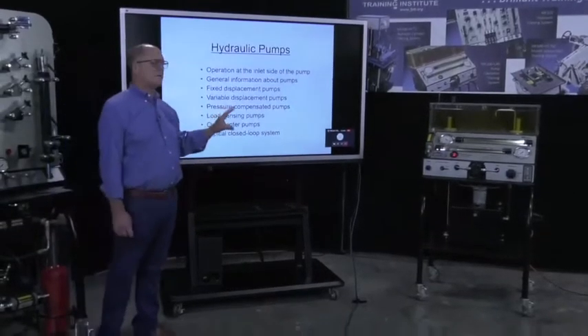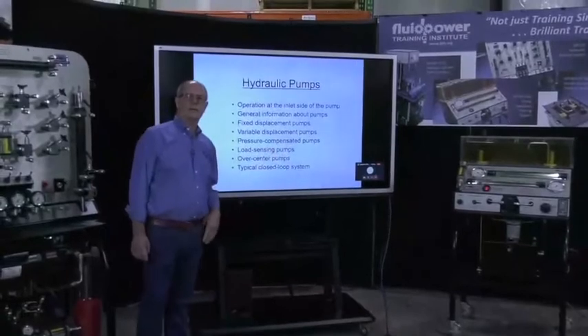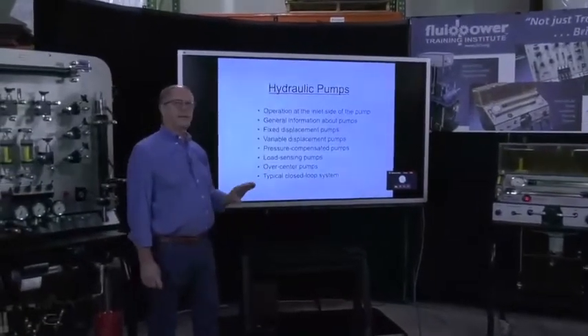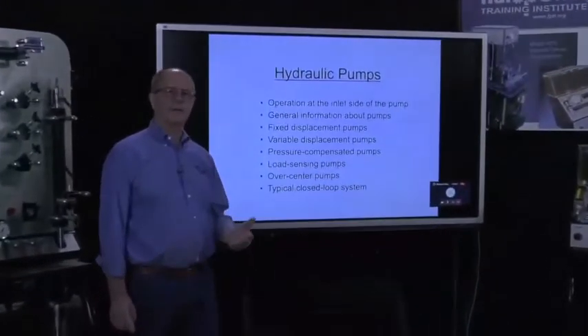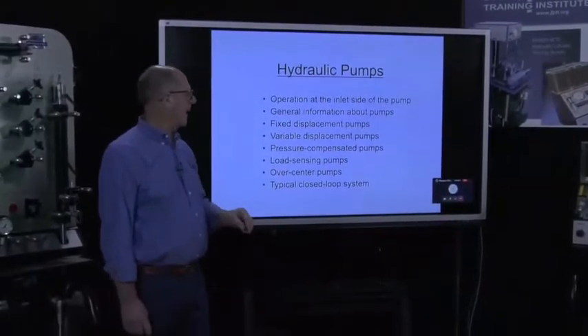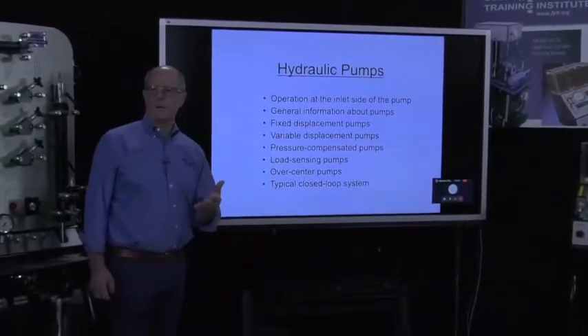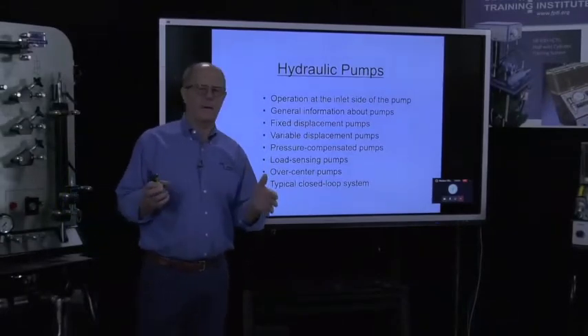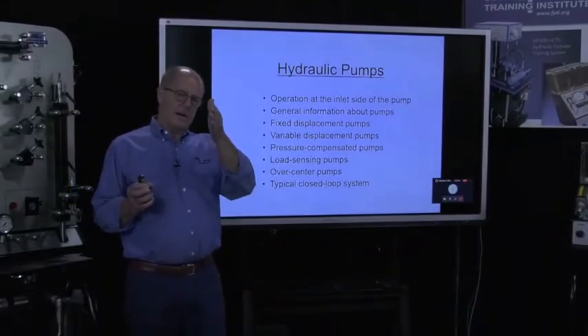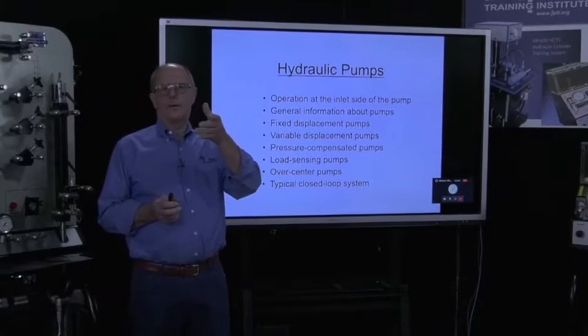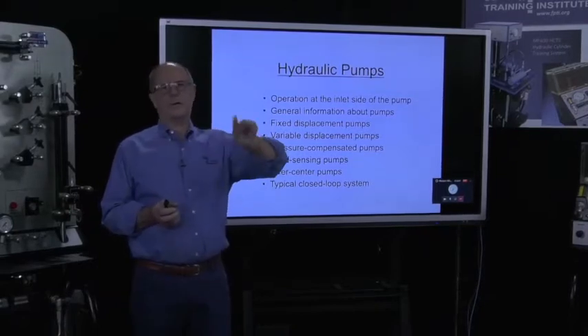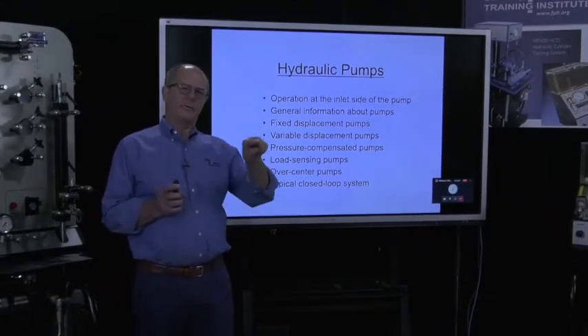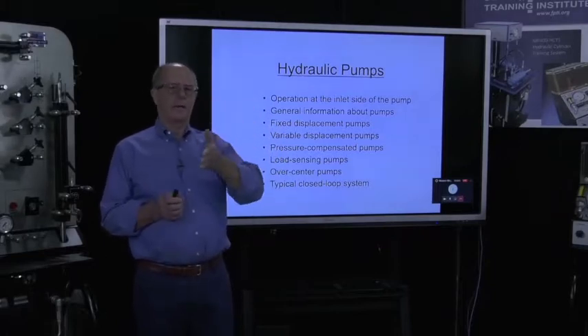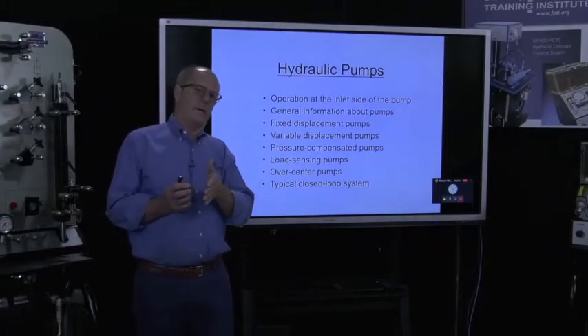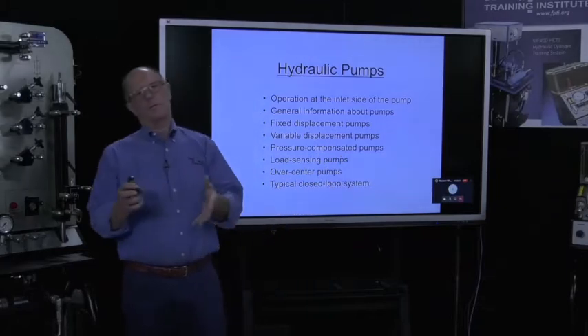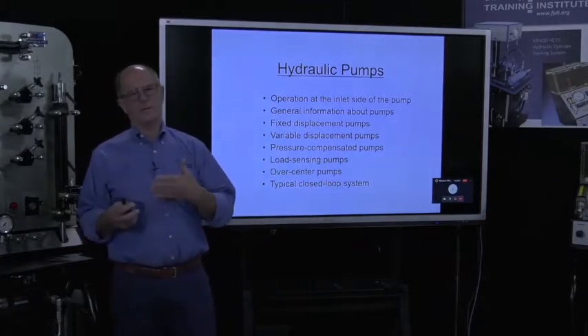All right, folks, what we have here is a PowerPoint presentation and our model MF200 CAV cavitation trainer, which is going to help us really understand this whole concept of cavitation and pseudo-cavitation. First and foremost, if you take a hydraulic pump and divide it through, let's say it's a 360-degree circle, and you divide it 0 to 180 degrees, the one side of it is the intake, and the opposite side, of course, is the pressure side where you obviously produce flow.